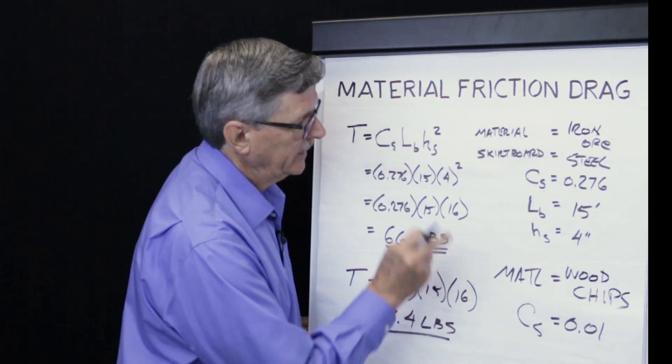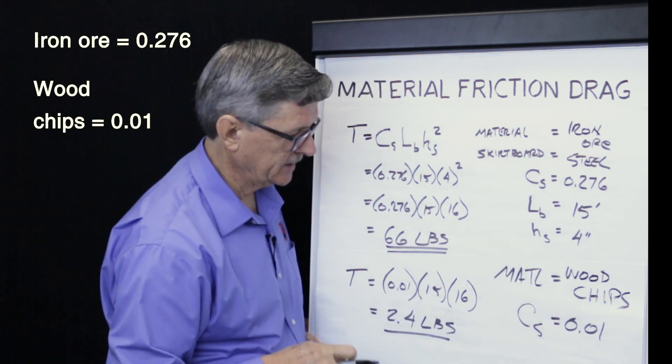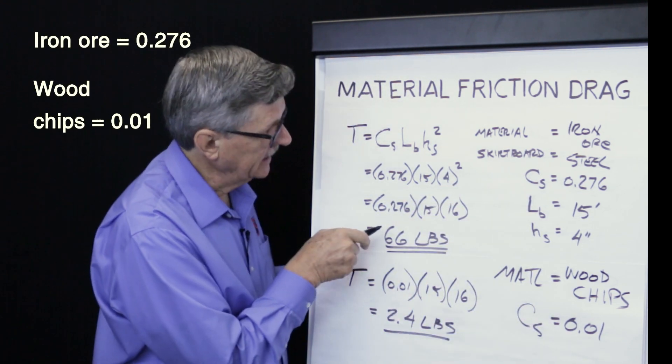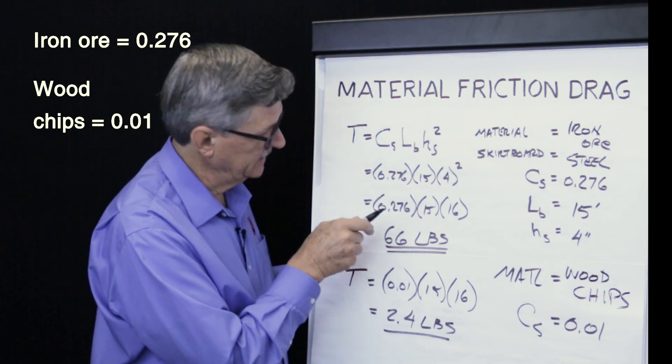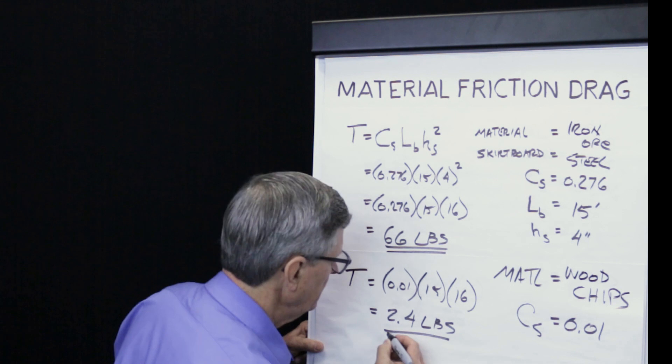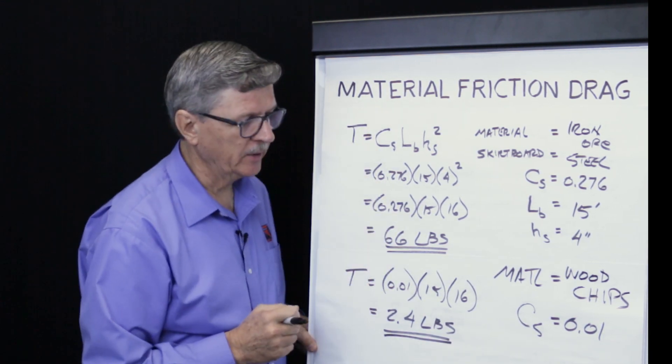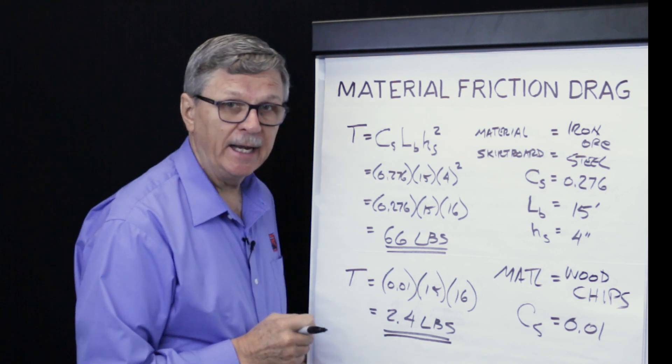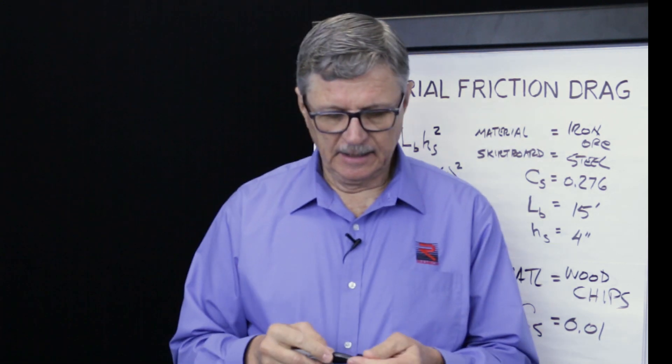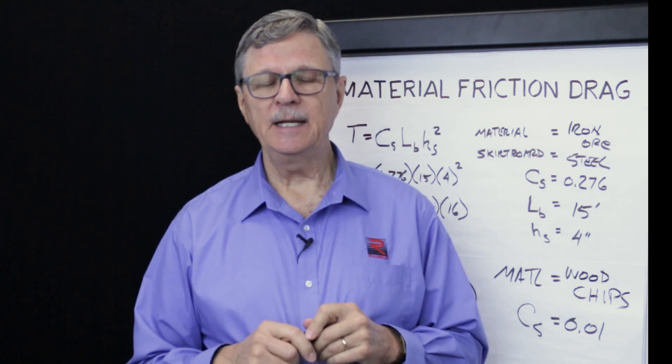This yields a result of 2.4 pounds. Notice that the frictional coefficient of iron ore is 27.6 times higher than that for wood chips. Therefore, the drag is 27.6 times higher, 66 pounds compared with 2.4 pounds. So now we've been able to calculate one of the two components of the skirt board system drag. CEMA gives a list of frictional coefficients to make it convenient to do this analysis.